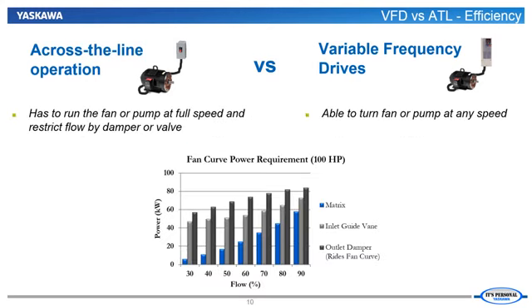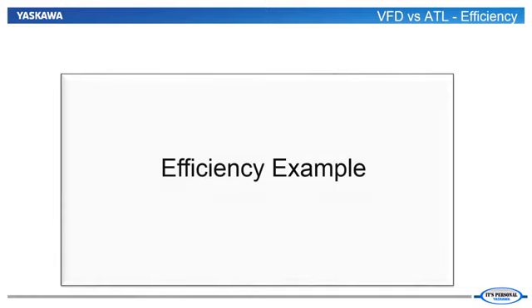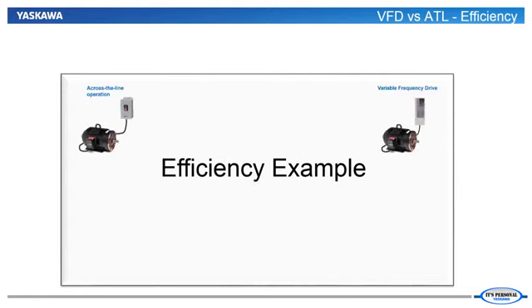Because the VFD has the ability to run the fan or pump only as fast as is necessary at any moment, it can afford great savings in operation versus the single-speed motor starter. Although use of an inlet guide vane on an across-the-line installation can achieve some energy savings as it reduces flow rates, it cannot match the much lower power usage afforded by the VFD being able to slow down the fan or pump. Let's take a look at an example that makes it easy to understand the savings you can unlock by running your fan or pump with a VFD instead of across the line.